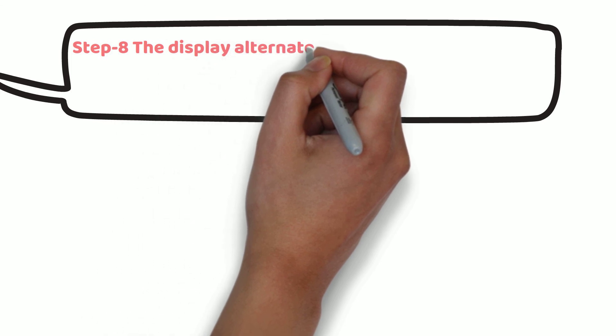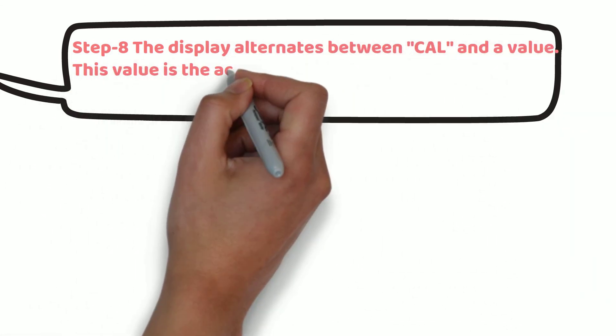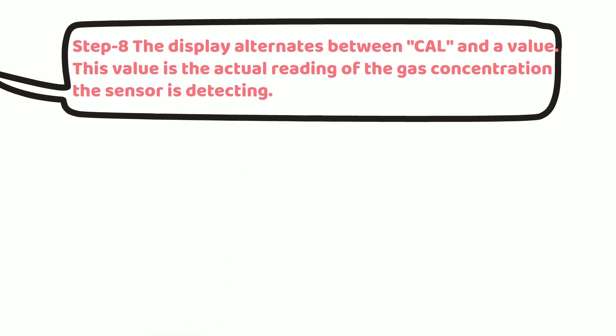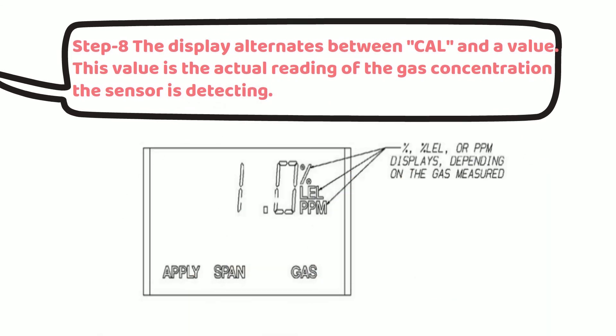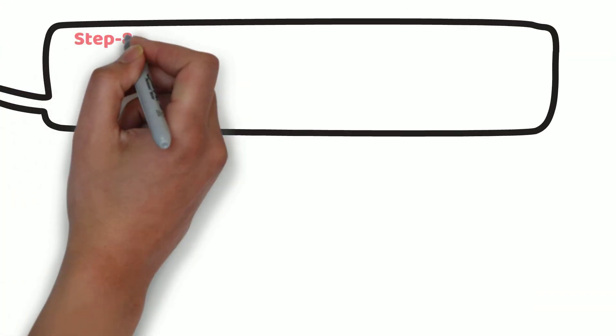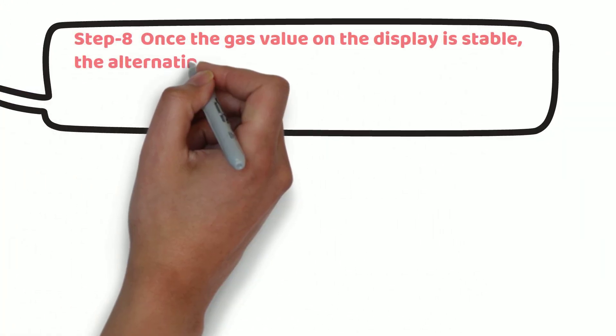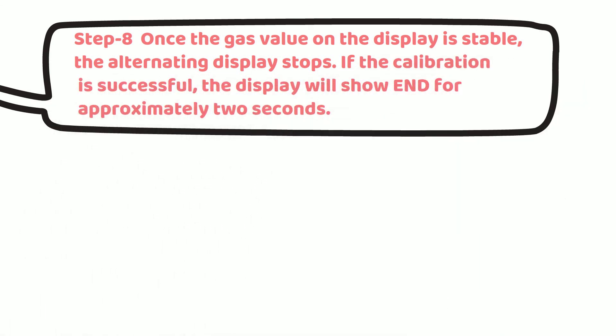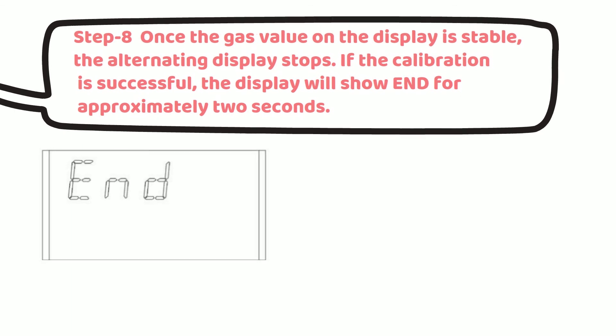The display alternates between cal and a value. This value is the actual reading of the gas concentration the sensor is detecting. Once the gas value on the display is stable, the alternating display stops. If the calibration is successful, then the display will show end for approximately 2 seconds.